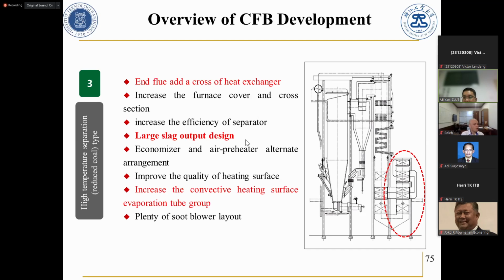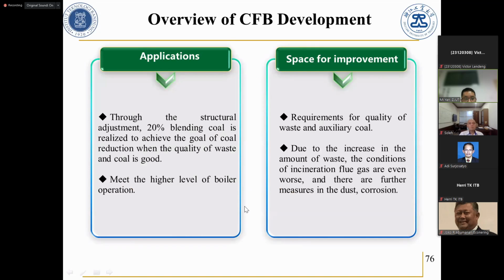Because some metal pipes in the MSW boiler easily block the slag output, we used larger slag output designs and increased the convective heat surface to evaporate the water. With this modification, we reduced the coal mixture ratio to less than 20%, meeting government requirements, and increased steam temperature to meet higher levels of boiler operation.